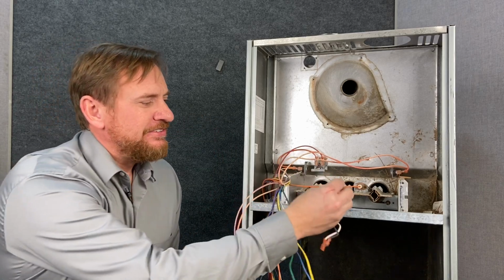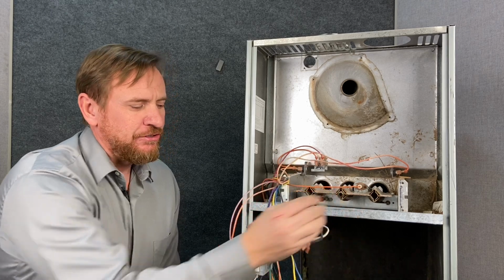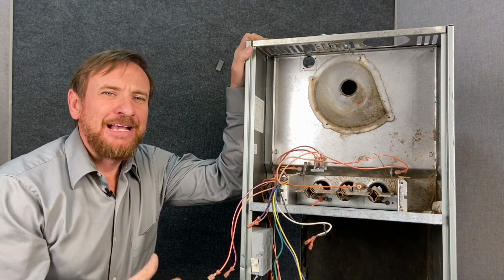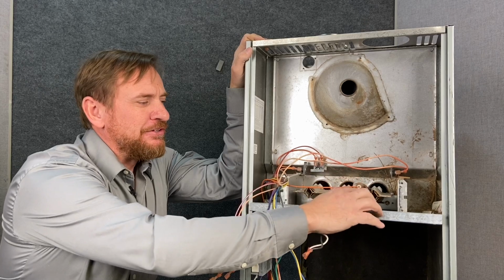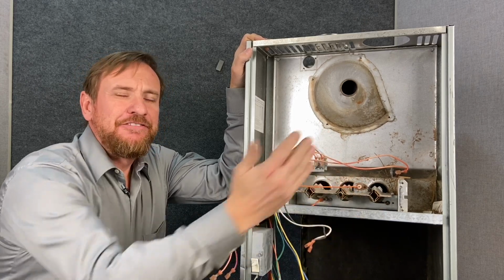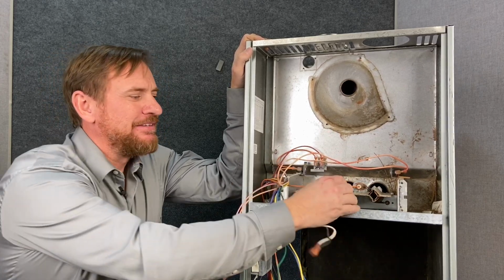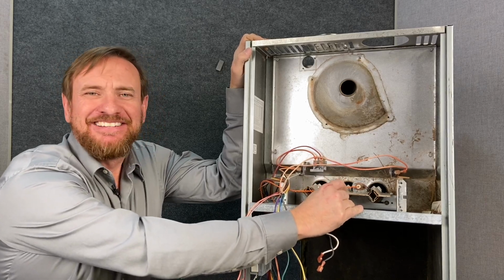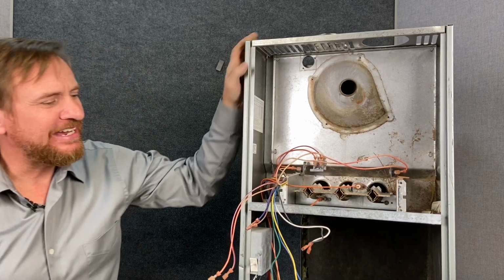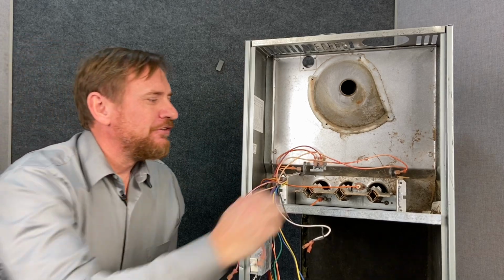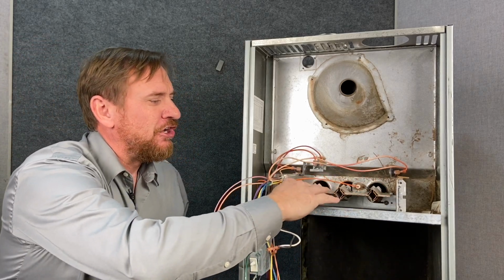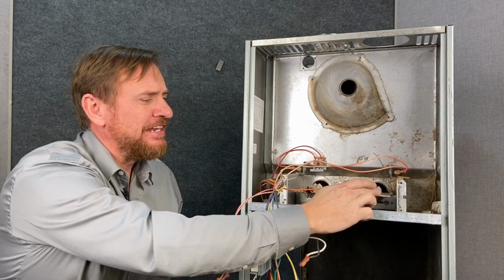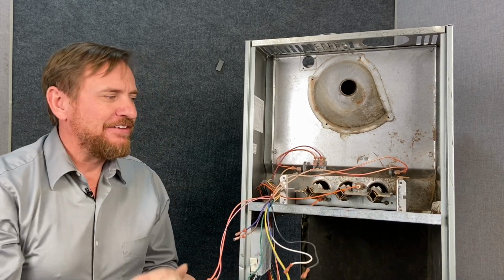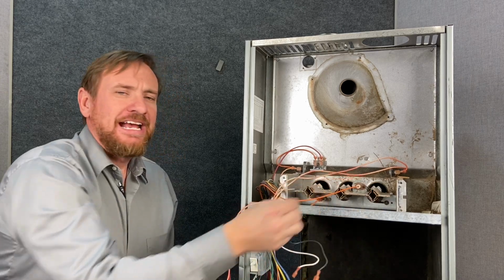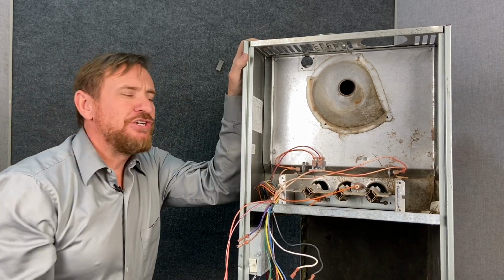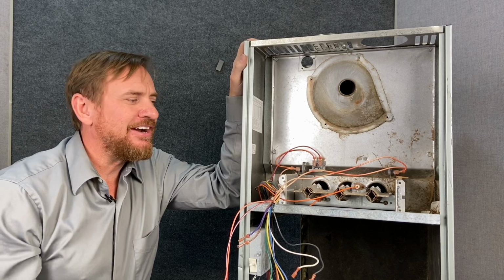What this orifice does is lines up here in our jets or our burners. There's many different types and styles of these burners, but these burners are called in-shot burners. In the field, a lot of people just call them jets. It's just a habit that's easy to get hung up in, and they look like jets. This particular style looks a little different than others. This one, Rheem and RUUD manufactures theirs all in one entire piece. It's all together. So this has 3 individual burners, and it has 3 of these spuds and orifices shooting gas into it. Now these burners have a main objective, to mix the primary air and the fuel.